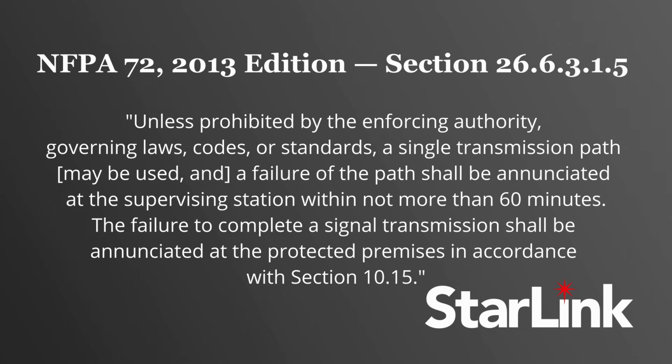The failure to complete a signal transmission shall be enunciated at the protected premises in accordance with Section 10.15. This section number carried forward through the 2016, 2019, 2022, and 2025 editions, but they dropped the 1 and renumbered it as 26.6.3.5 in the later editions.